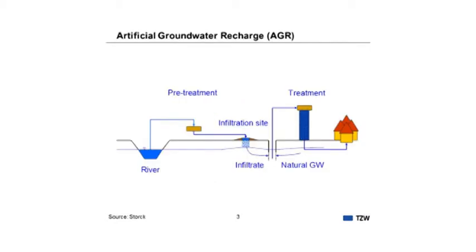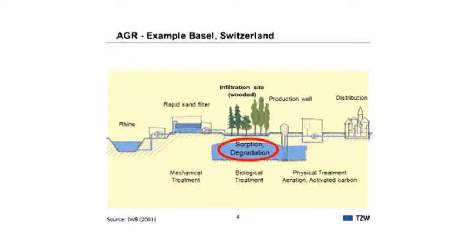Here is an example of an artificial groundwater recharge site. This is Basel in Switzerland, where the water of the river Rhine is used. It undergoes pretreatment in rapid sand filtration, and afterwards it is infiltrated in wooded infiltration sites. This is where the main removal of organic trace pollutants and DOC takes place. Finally, there are production wells and some treatment for physical stabilization and disinfection. This is an impression of such a wooded infiltration site in Basel.